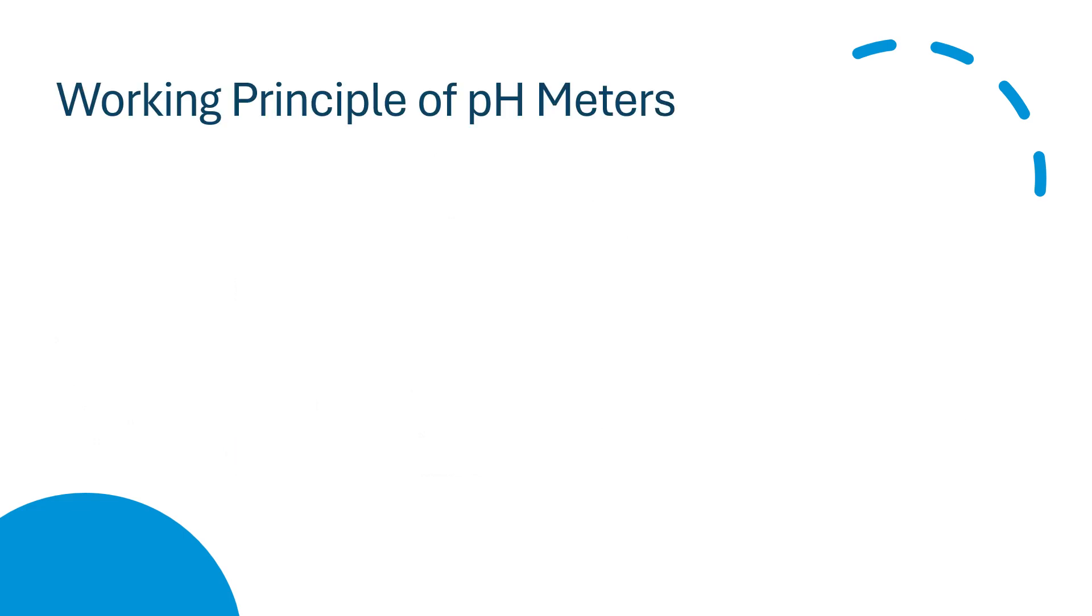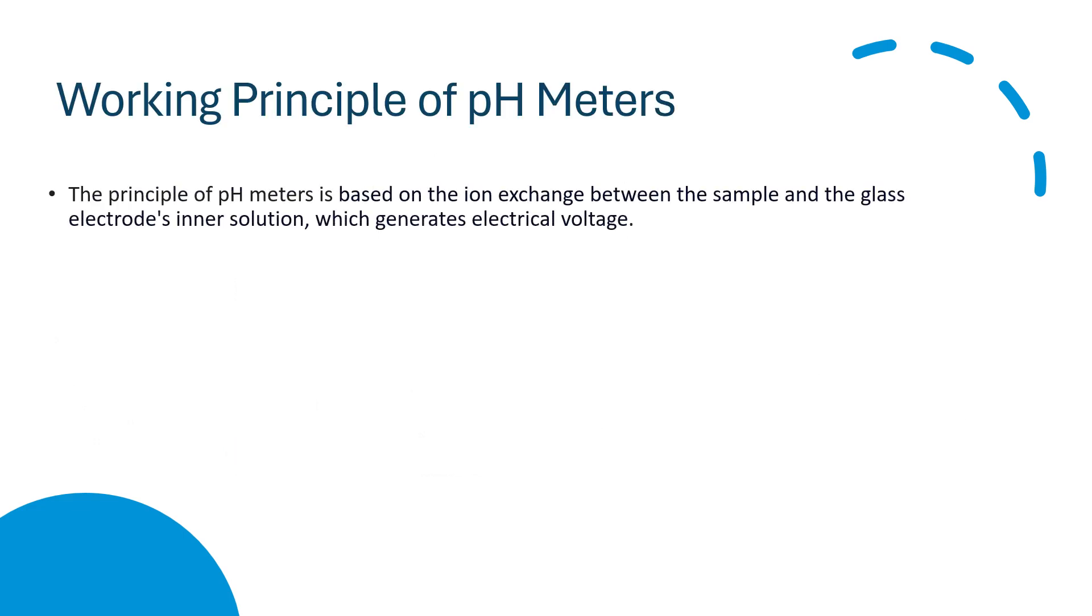Now we will discuss the working principle of the pH meter. The principle of the pH meter is based on the ion exchange between the sample and the glass electrode's inner solution which generates electrical voltage. That means hydrogen ions interact with the glass electrode, generating a potential that is measured against the stable potential from the reference electrode. Then the meter converts this potential difference into a pH value.